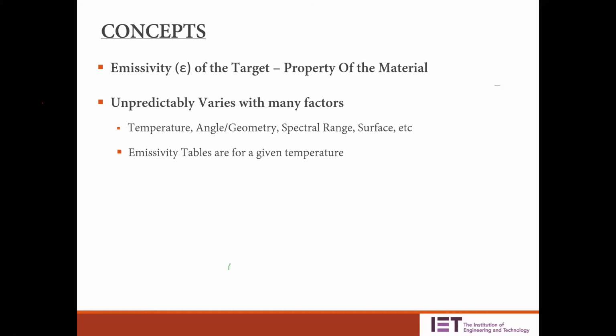Some professionals in the trade tend to refer to these emissivity tables given for certain materials. Say they are trying to measure a copper bus bar temperature, so they look at the table and try to get the emissivity from there, which is not the best practice and can lead to many errors in the reading.